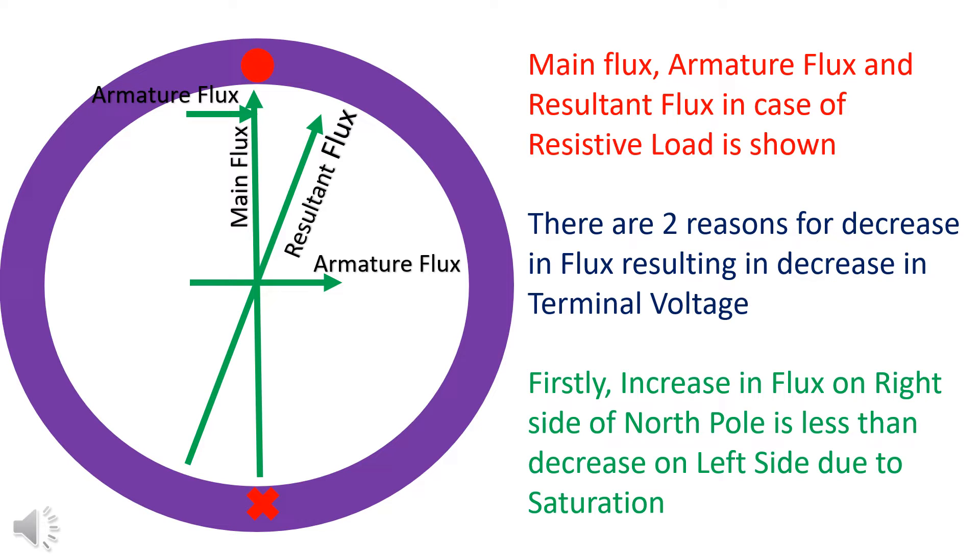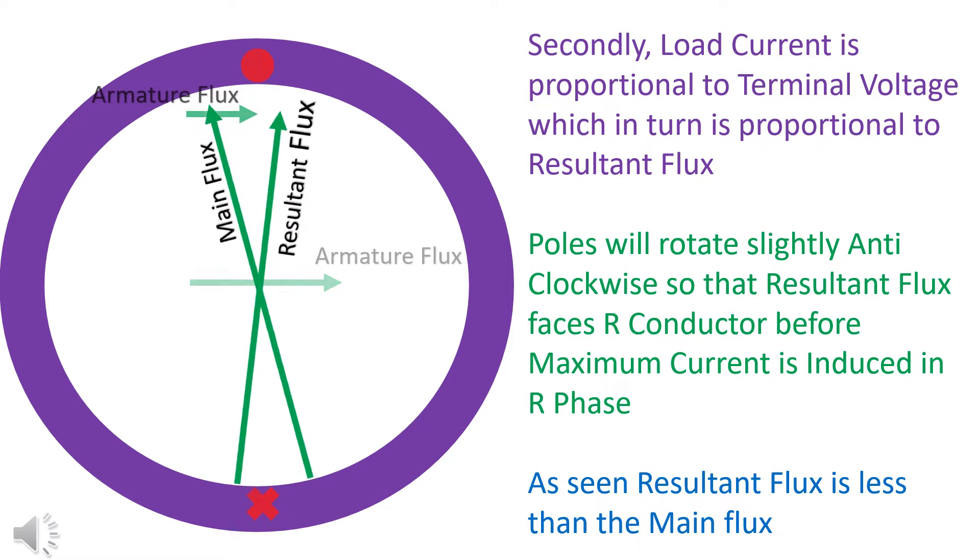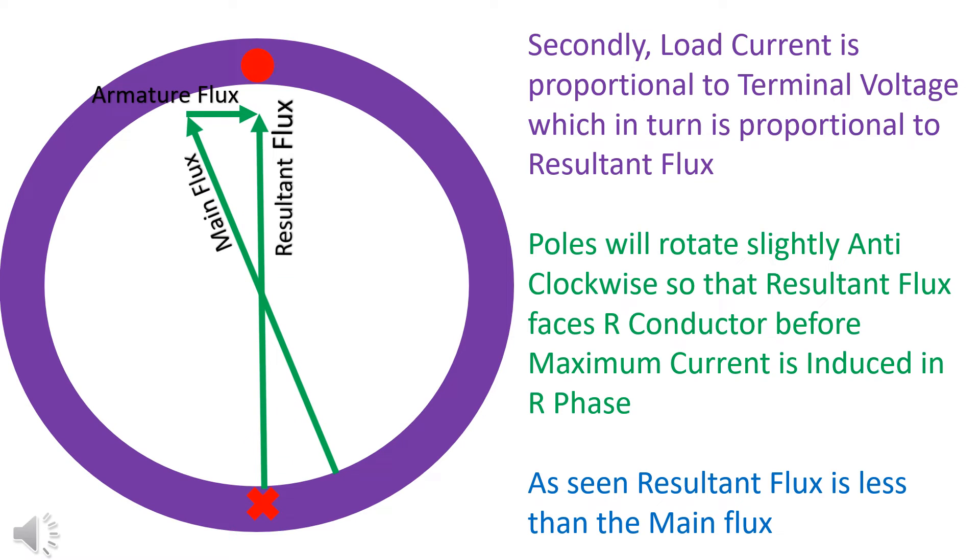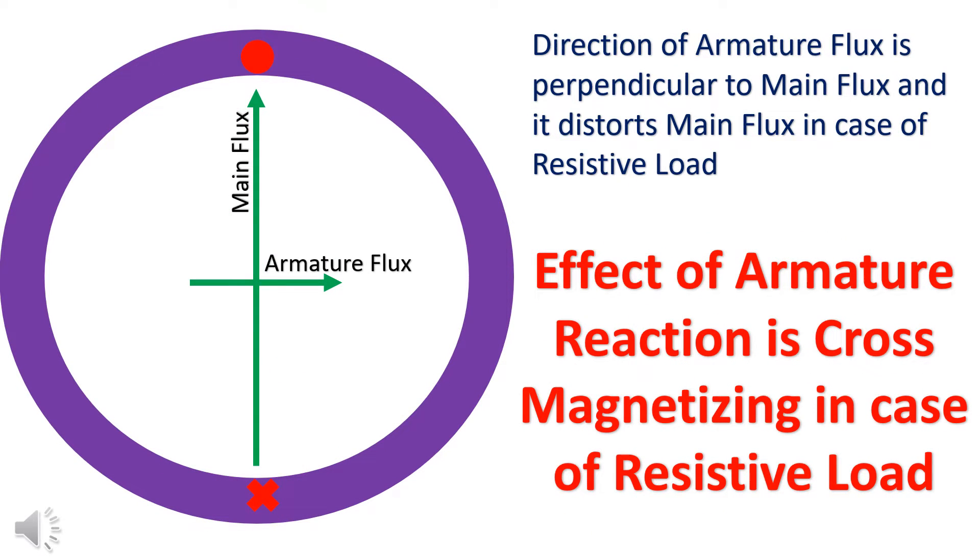There is slight decrease in the average flux. Firstly, increase in flux on one side is less than that on the other side due to saturation. Secondly, resultant flux is a phasor sum of the main flux and the armature flux. Resultant flux is less than that of the main flux. Since in the case of resistive load, there is increase in flux on one side and decrease in flux on the other side of coil, the effect of armature reaction is cross-magnetizing.